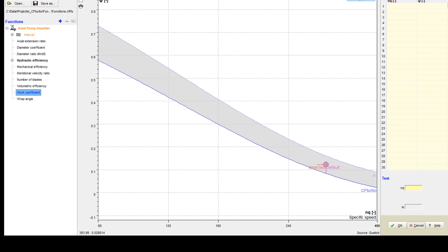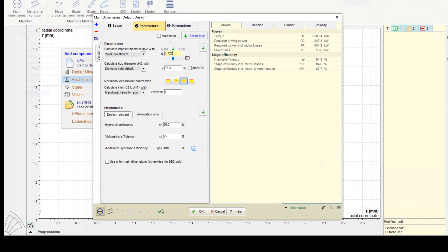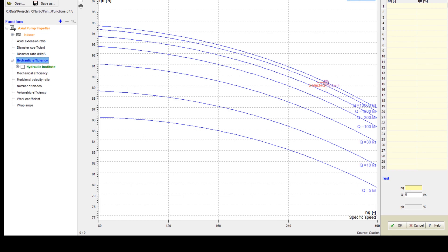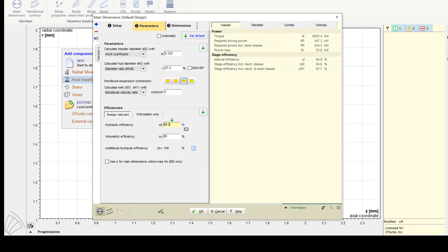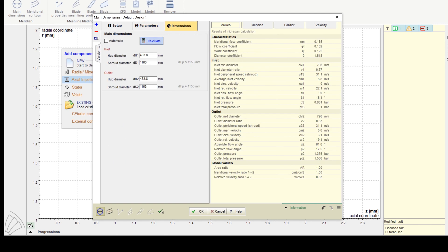To calculate the impeller main dimensions, CF Turbo uses empirical correlations. Here we apply the work coefficient to calculate the impeller diameter and a diameter ratio function to get the hub diameter. Additionally, there are empirical functions to estimate the pump efficiency.